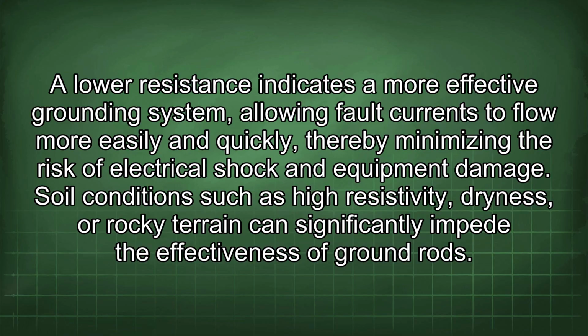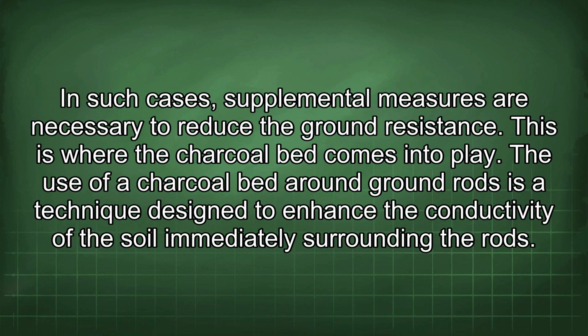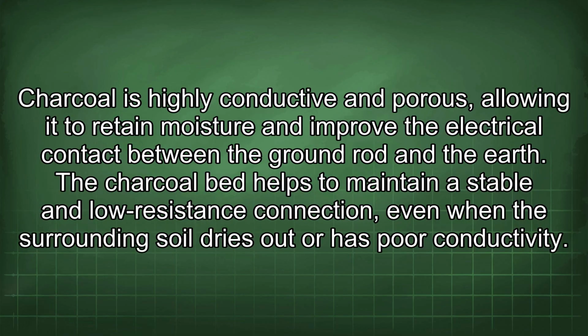Soil conditions such as high resistivity, dryness, or rocky terrain can significantly impede the effectiveness of ground rods. In such cases, supplemental measures are necessary to reduce the ground resistance. This is where the charcoal bed comes into play. The use of a charcoal bed around ground rods is a technique designed to enhance the conductivity of the soil immediately surrounding the rods. Charcoal is highly conductive and porous, allowing it to retain moisture and improve the electrical contact between the ground rod and the earth.